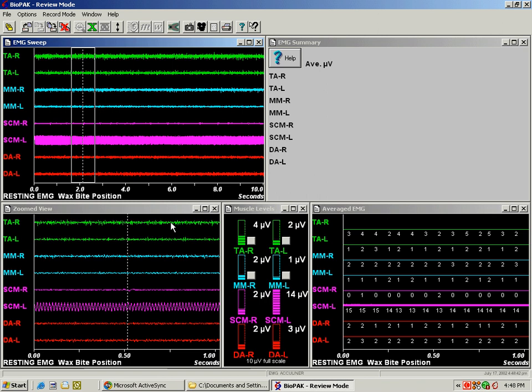As long as the electrode connections and everything was set up correctly, BioResearch has designed a program called the Noise Buster that will obviously by seeing the electrical noise you'll be warned there is noise there, be able to address that in the future.